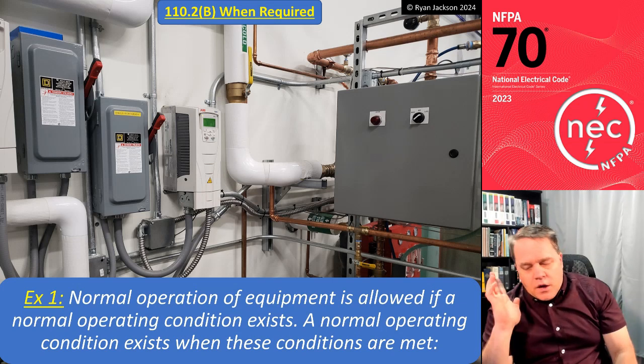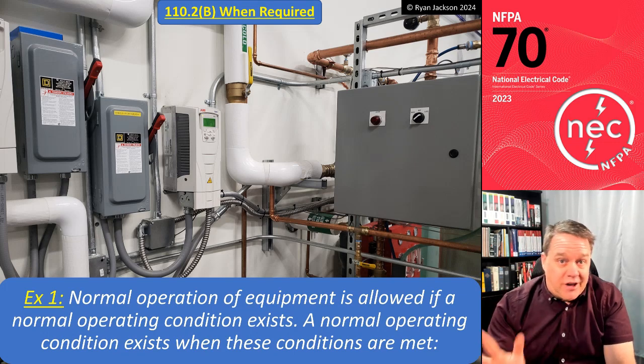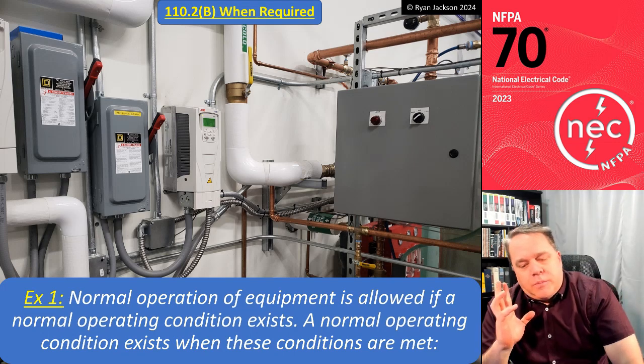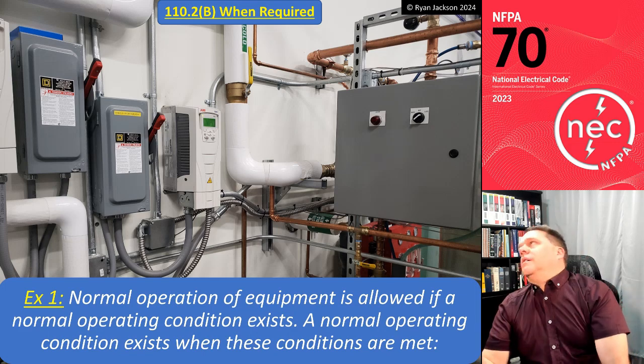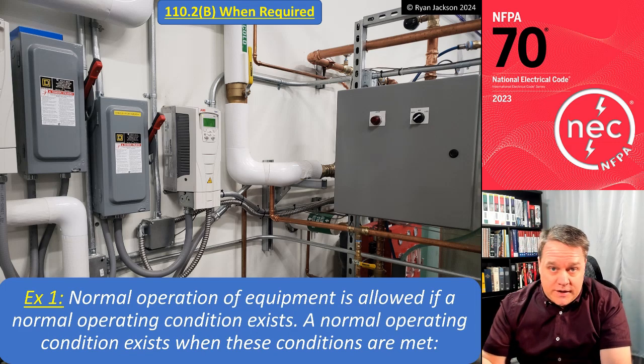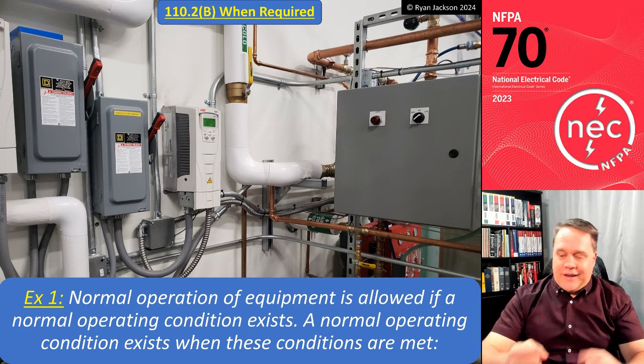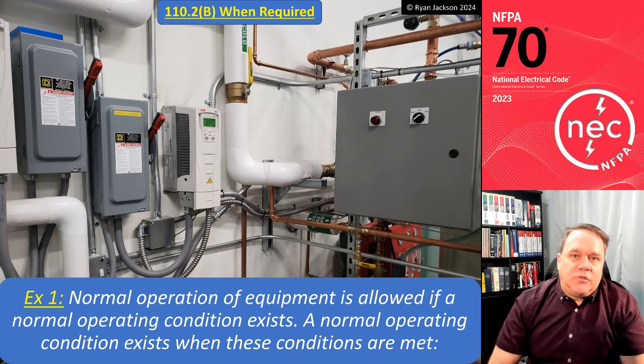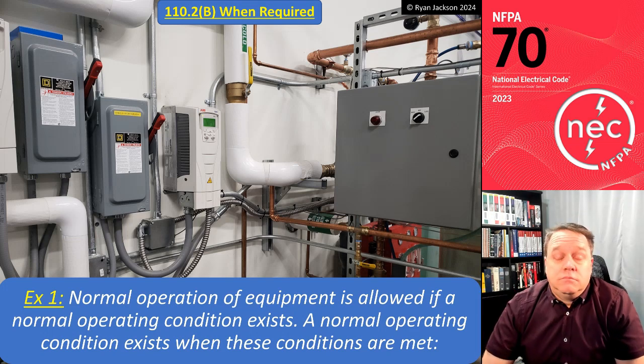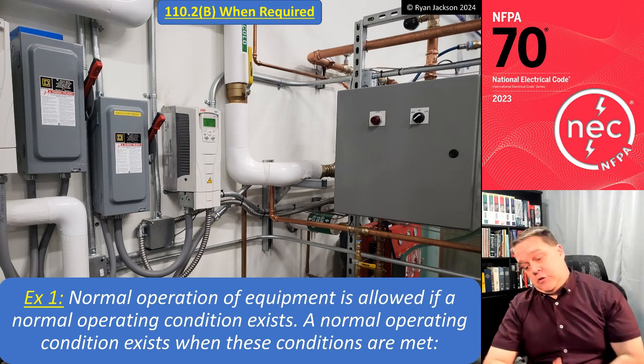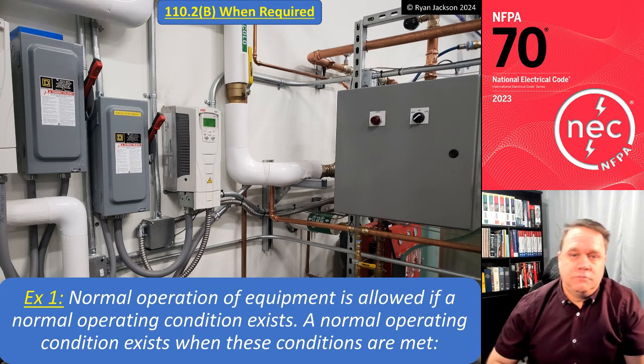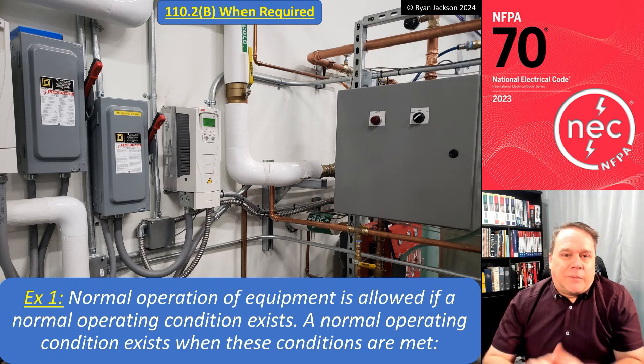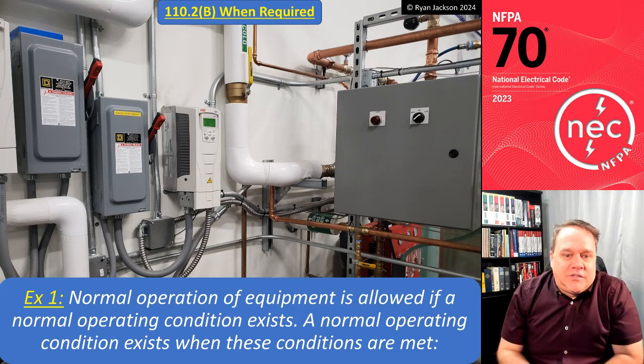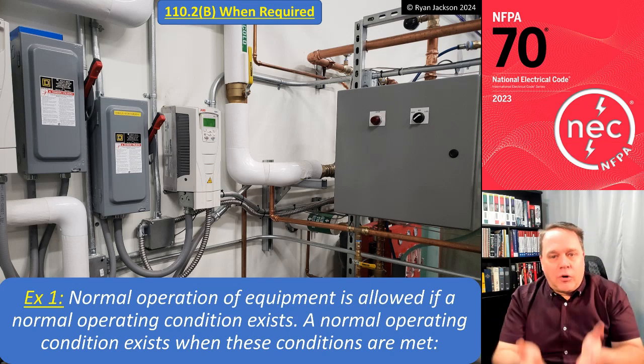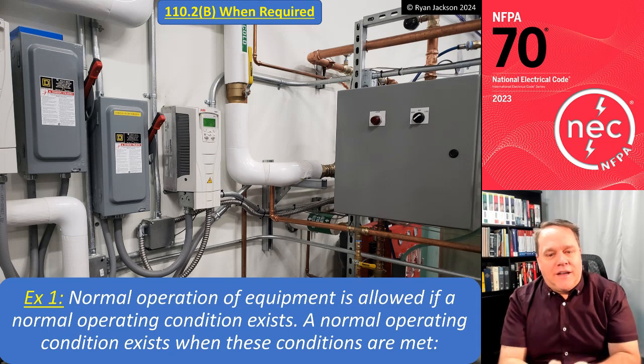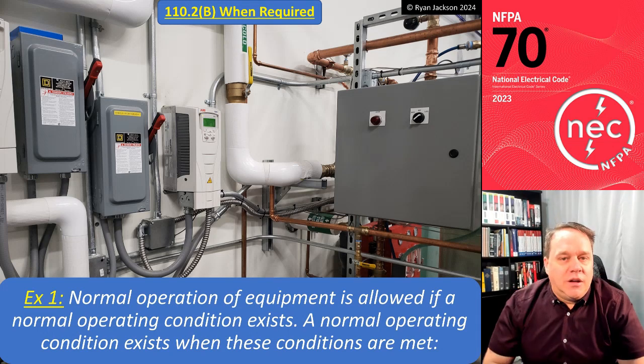All right, there's a massive misconception here, and I kind of already talked about it, where people roll their eyes and they say, oh my God, NFPA 70E, holy cow. You got to dress up like an astronaut to turn on a light switch. No, you don't. Well, but you do to plug a thing in. No, you don't. Stop pretending you know what the standard says if you've never read the standard. It doesn't say that. It says normal operation of equipment is allowed if a normal operating condition exists.